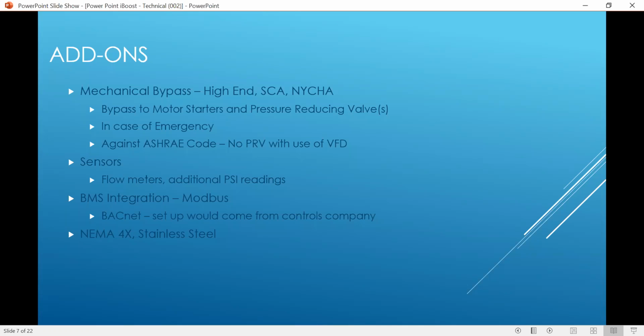Mechanical bypass. You can do a bypass mode for the motor starters, not run off the drives if you want to. We don't recommend that, because with our new technology, our systems run off a program in the PLC. The drives are really there to throw themselves on a grenade in the event of a high voltage situation or something that would affect the electrical circuitry. So the drive will protect the motor and keep you from having to purchase a brand new motor as well as a drive if a drive were to go out. On the ABBs, everybody's pretty familiar with them, so we like to stick with them.